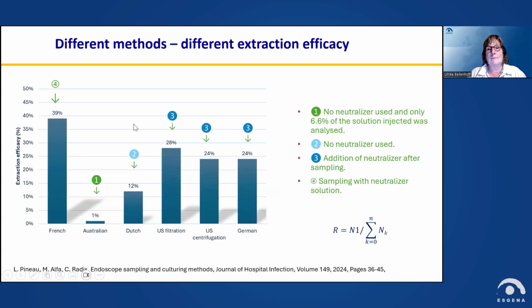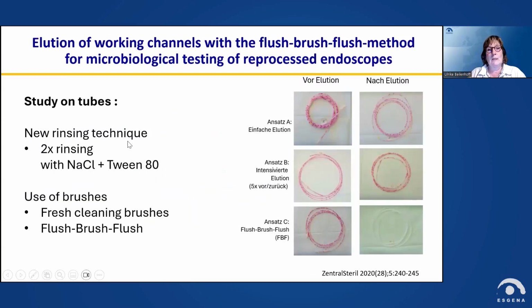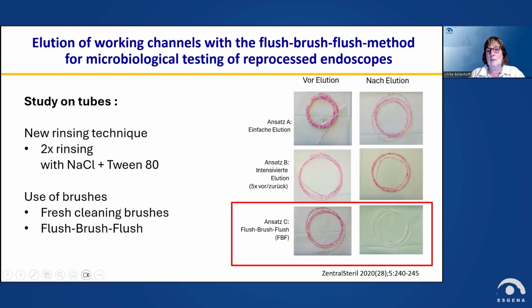It is also clear that the solution you use has an impact on the microorganisms you later find. So there is also the recommendation to use neutralizer, because the disinfectant which is just left on the endoscope can also kill the microorganisms later in your sampling solution. So that seems also to have an impact. In Germany, we also checked this increased sampling method with the flush-brush-flush method. And you see here that if you use this, you can really clean the tube, that are the endoscope channels. So that seems to have an effect, that if you use an increased sampling method, you have a more sensitive method.